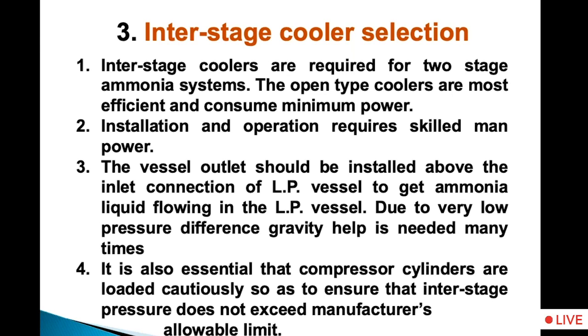Then this vessel has to be kept outside the plant room. LP vessel and interstage cooler have to be kept outside the plant room. So when you are designing a new plant, if you are using an open interstage cooler, design the plant room for 15 to 20 feet plant room height. This is the most efficient interstage cooler, but difficult to handle, difficult to operate also.